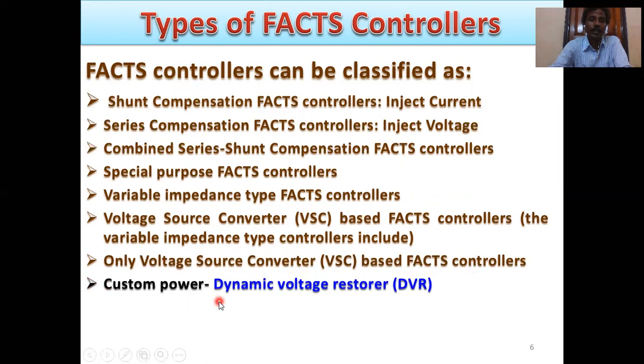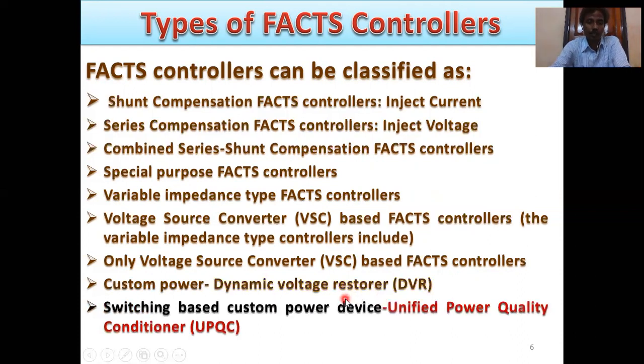Custom power. This is also a very important part. Dynamic voltage restorer is a series connected custom power device. It injects voltage and compensates sag, swell, flicker, and any type of voltage distortion. Switching based custom power device is also very, very important. Unified power quality conditioner controls the power quality.